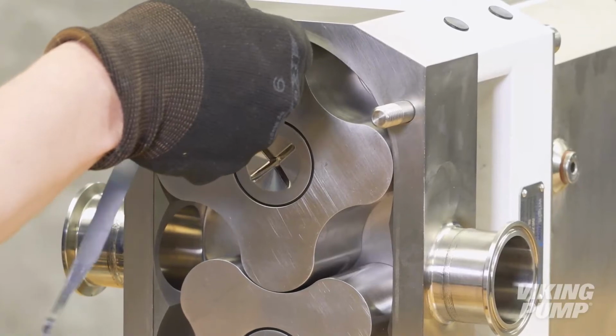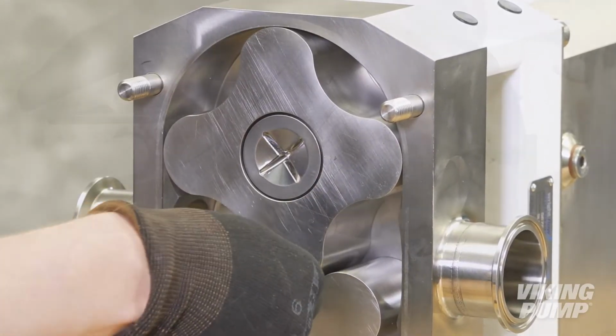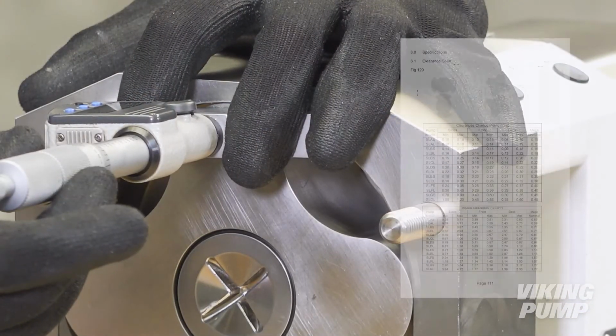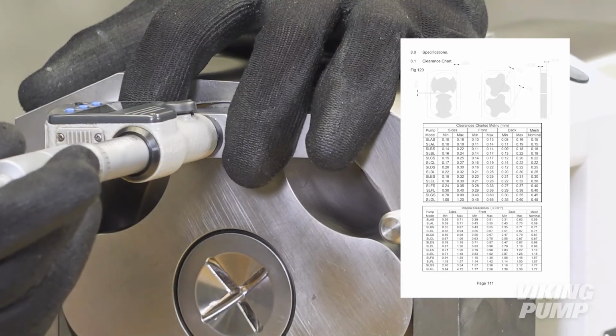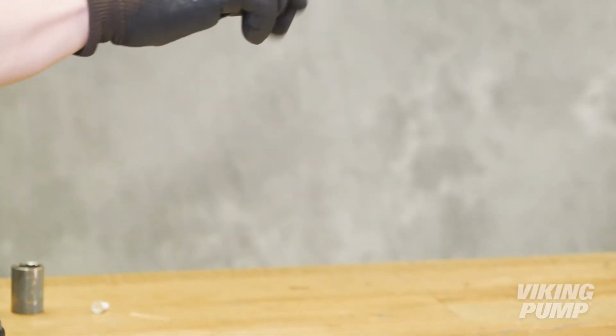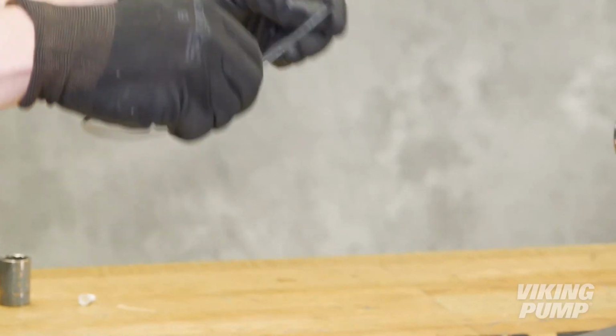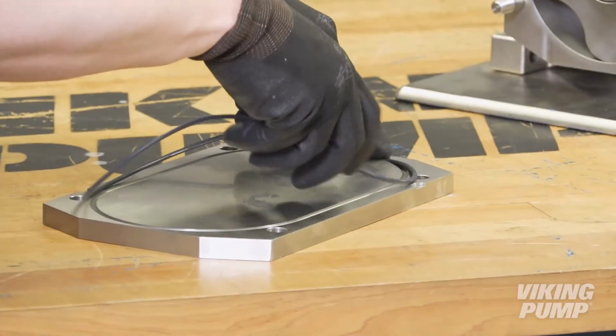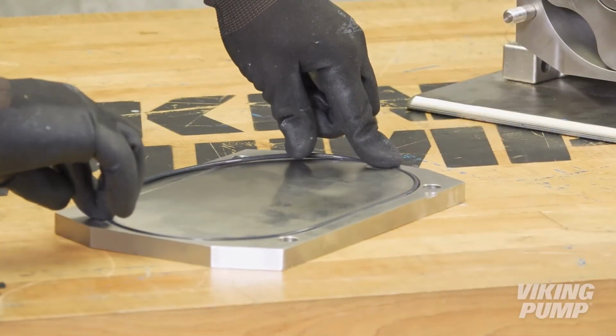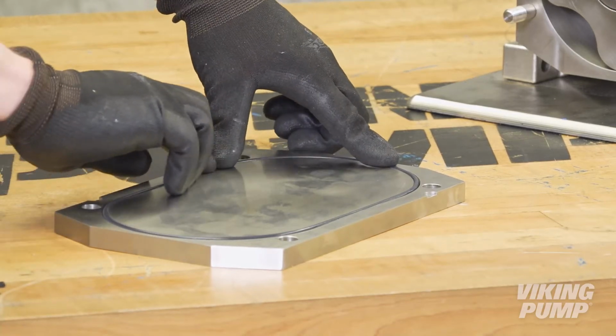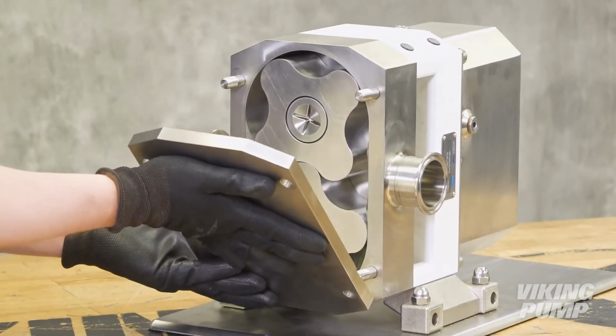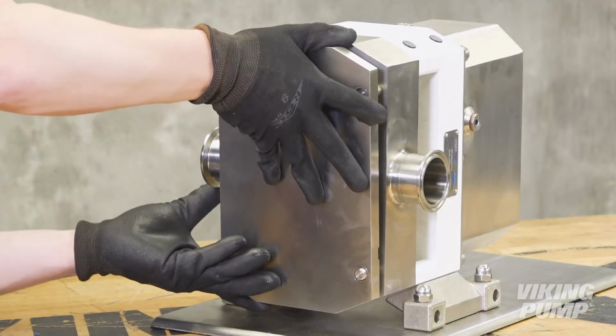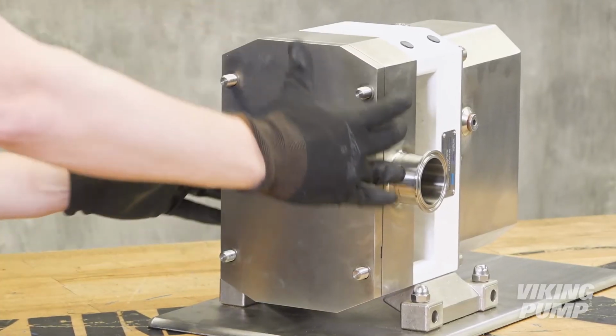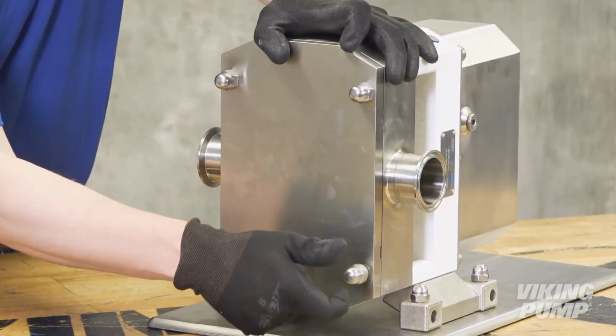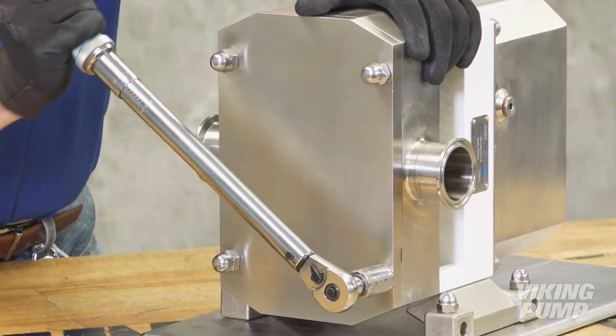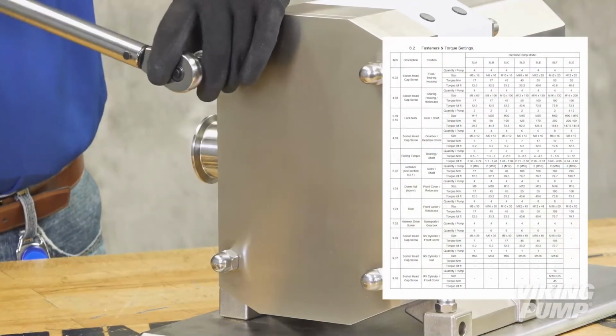Check clearances using feeler gauges and a depth micrometer. Adjust shims as needed and per the recommendations in the service manual. Once correct clearances have been confirmed, lubricate and install the front cover O-ring. Reinstall the front cover and dome nuts. Torque the dome nuts to the appropriate setting as listed in the service manual.